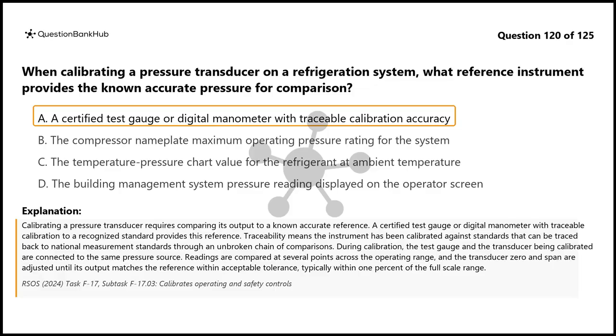During calibration, the test gauge and the transducer being calibrated are connected to the same pressure source. Readings are compared at several points across the operating range, and the transducer zero and span are adjusted until its output matches the reference within an acceptable tolerance, typically within 1% of the full-scale range.